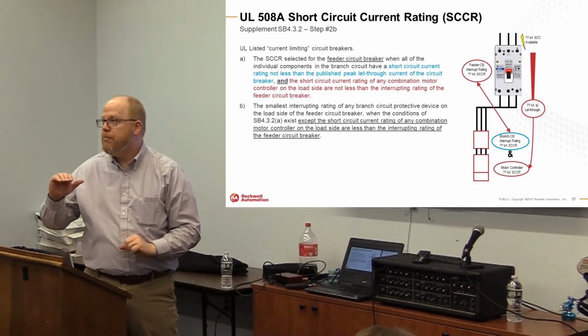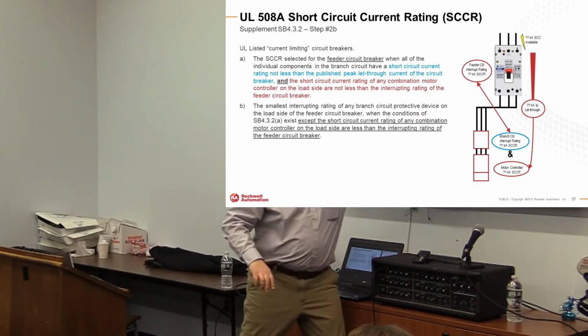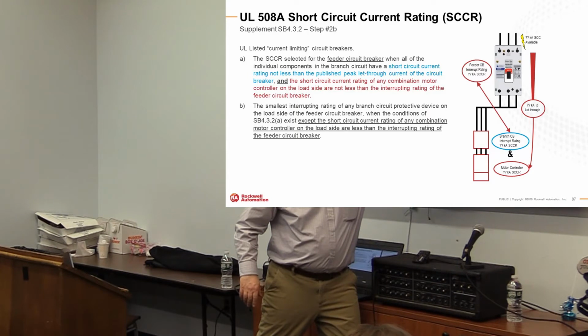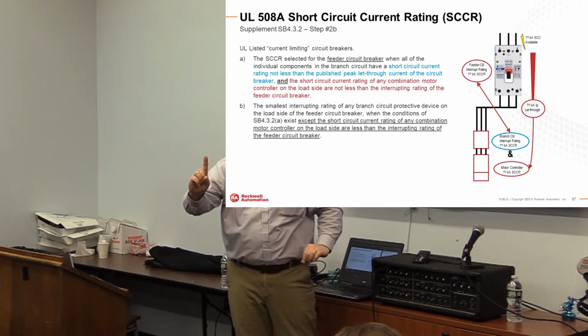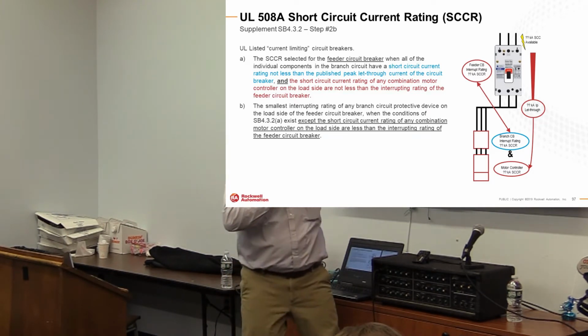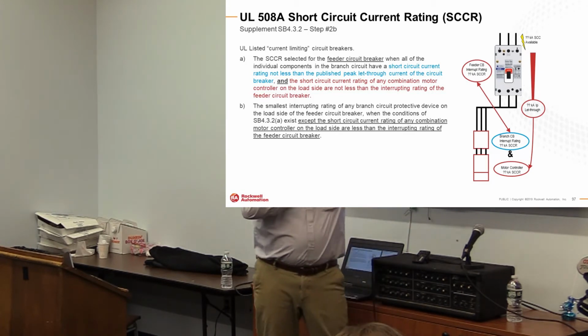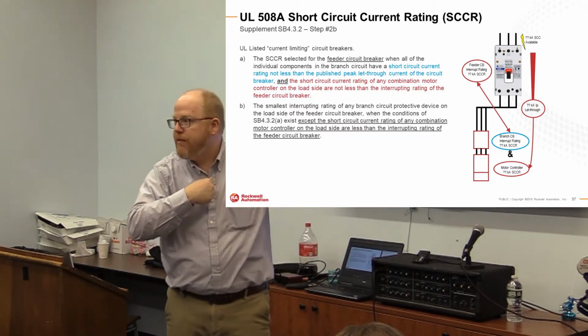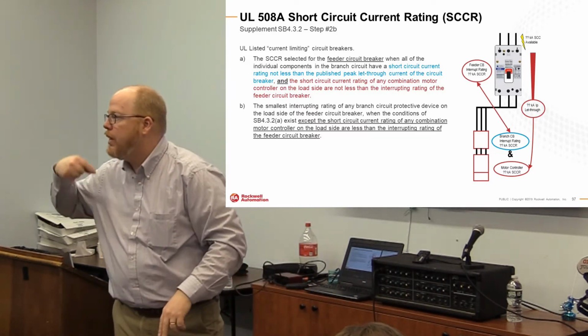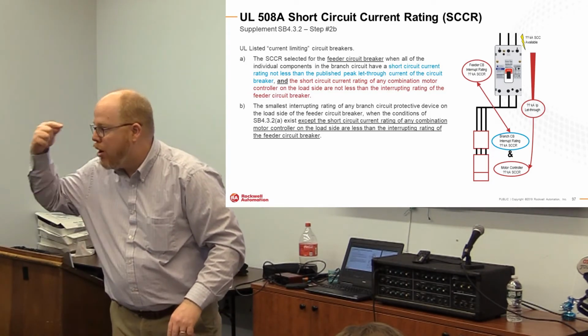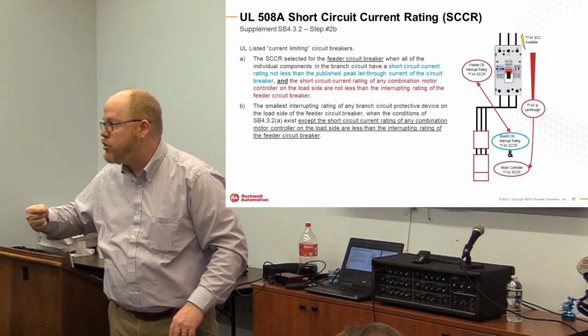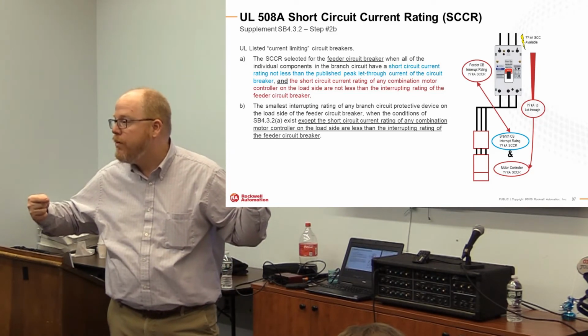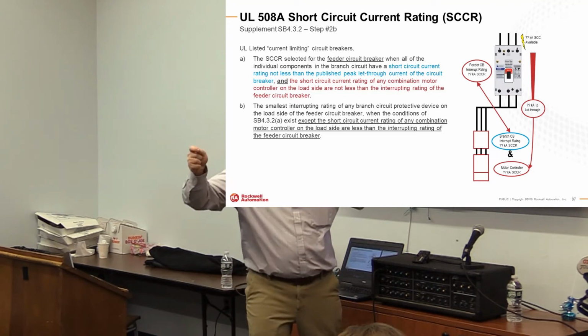Okay, when all these components have a short circuit current rating not less than the published peak let-through current of the circuit breaker. So a data point you need to do this evaluation from a manufacturer of the breaker is a thing called a peak let-through current. You all understand that if you're subject to an available fault of 65,000 amps, these are engineered devices that have a lag in response. And you could get a partial cycle of current that comes downstream and blows these little guys up downstream. That's what we're talking about for peak let-through. It's a partial cycle, okay? Now, so that's the part in blue.